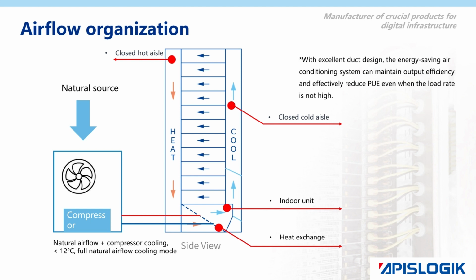Outdoor ambient temperature less than 12 degrees Celsius: pure natural cooling mode. Outdoor ambient temperature greater than 30 degrees Celsius: compressor mode. Outdoor ambient temperature from 12 degrees Celsius to 30 degrees Celsius, inclusive: hybrid mode.